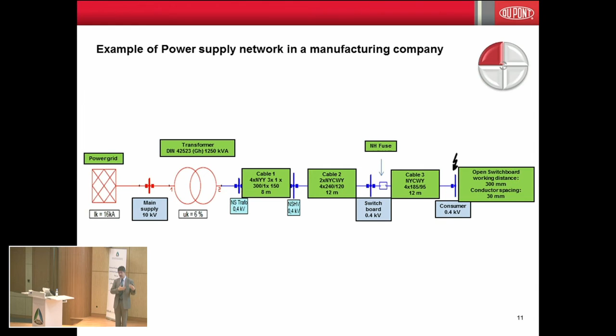In this case, the incident energy calculated for an incident at 300 millimeters was 42.57 calories per square centimeter. If you remember, 1.2 is the level for a second-degree burn, so you can understand that more than 42 calories will potentially even have a death impact on the person, because you are at very high levels of energy.